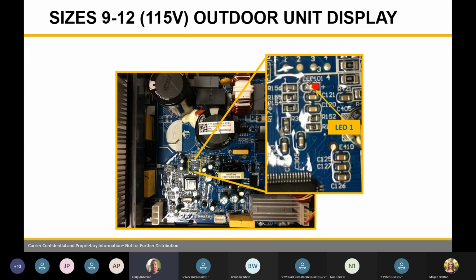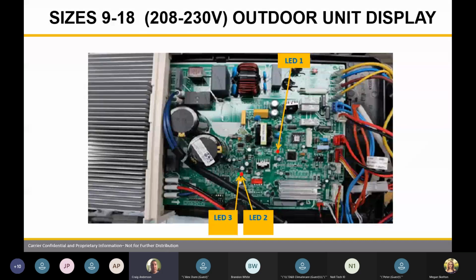9 to 18,000s, the 208 volt, 230 volt units. We're looking at 3 LED lights. So each LED light will give you an idea of what's going on. One will be blinking, one will be solid on. So those are things to look at when we're looking at an outdoor unit.